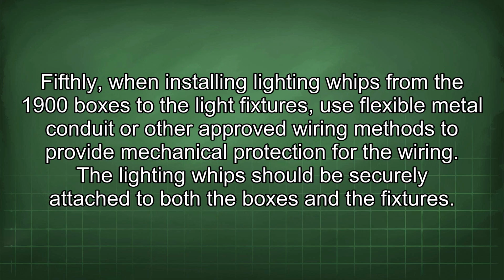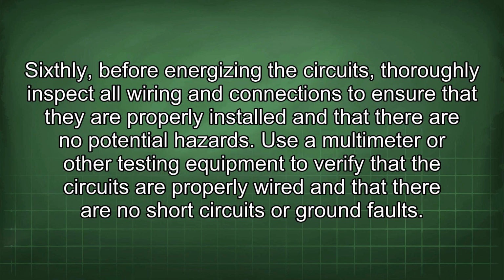Fifthly, when installing lighting whips from the 1900 boxes to the light fixtures, use flexible metal conduit or other approved wiring methods to provide mechanical protection for the wiring. The lighting whip should be securely attached to both the boxes and the fixtures. Sixthly, before energizing the circuits, thoroughly inspect all wiring and connections to ensure that they are properly installed and that there are no potential hazards. Use a multimeter or other testing equipment to verify that the circuits are properly wired and that there are no short circuits or ground faults.